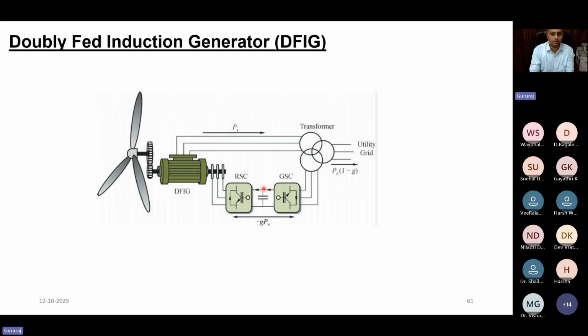The DC link capacitor in itself is not an energy source. It's just a temporary energy storing element which can maintain the voltage at a certain level. So if you take active power out of this DC link capacitor, there is a dip in voltage, right? This dip in voltage needs to be compensated by another converter, which is called the grid side converter. And how does it do that? It would carry power from the point of common coupling and try to maintain this DC link voltage constant, and ensure that the lack of power expected at the machine side is taken back from the same point of common coupling indirectly.